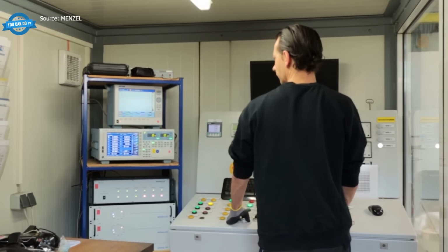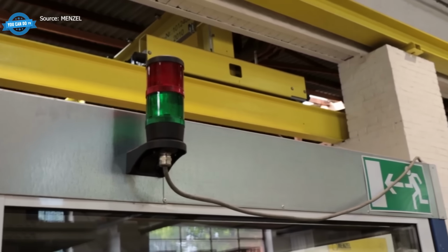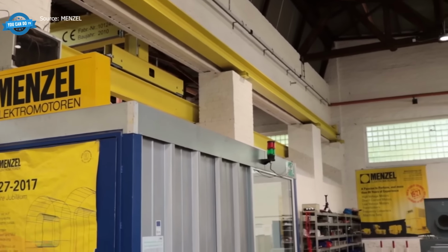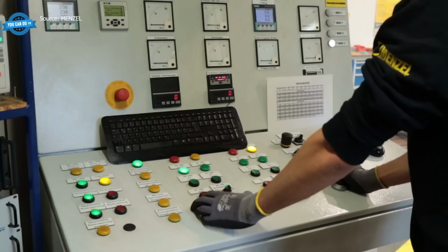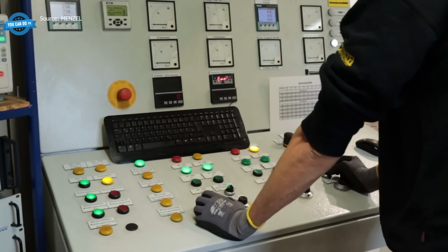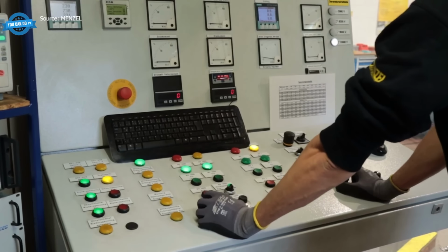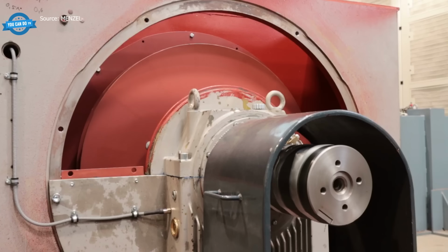The last piece of the drive system is the motor that actually turns the load, and starting a 3,000 kilowatt motor under heavy inertia is a different engineering problem from running it at steady state. A three-phase asynchronous slip ring motor rated at 3,000 kilowatts and 10,500 volts takes 90 seconds to accelerate from standstill to 993 revolutions per minute on a test bench.